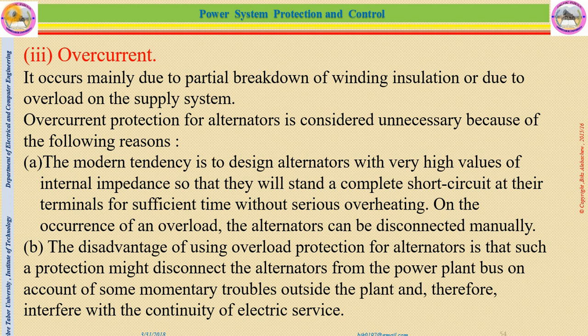The first one: modern tendencies are to design alternators with very high values of internal impedance, so they will stand a complete short circuit at their terminals for sufficient time without severe overheating. That means due to that internal impedance. On the occurrence of overload, the alternator can be disconnected manually, so there is no need of automatic protection. The second reason is that the disadvantage of using overload protection for the alternator is that such protection may disconnect the alternator from the power plant bus on account of some momentary trouble outside the plant, and therefore they interfere with the quality of the electrical service.